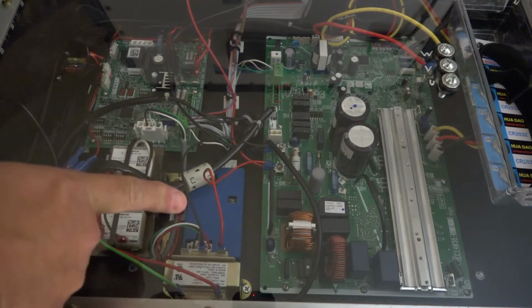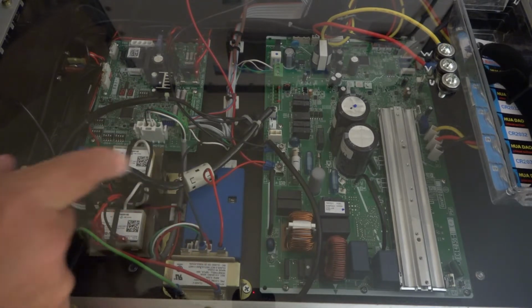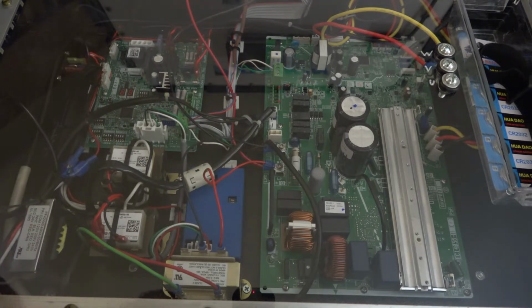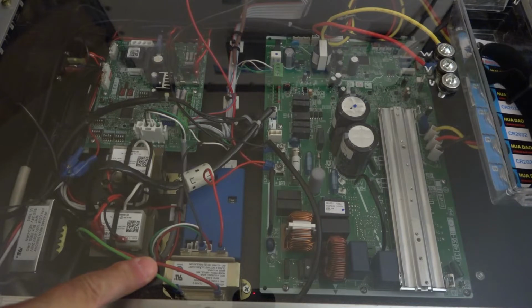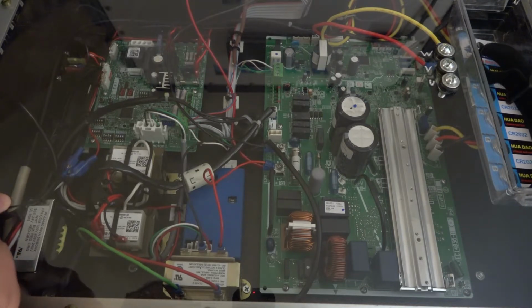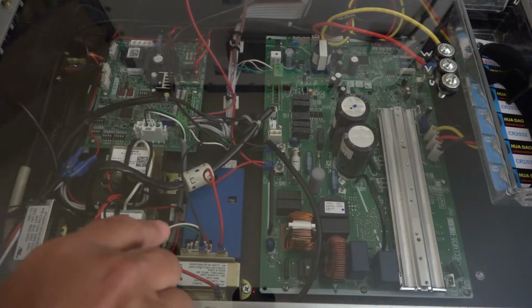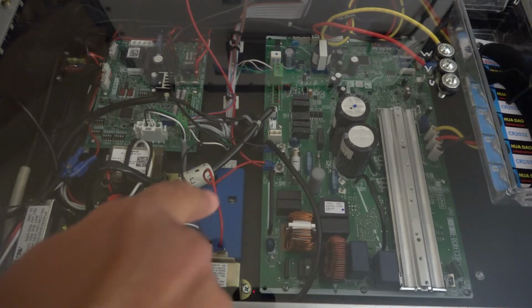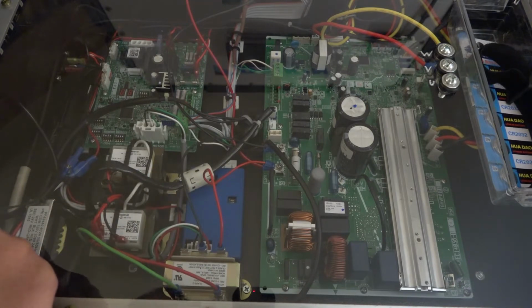The little blue box here is an ECM motor simulator. Now what I've done, I've got 120 volts powering this box. So I'm bringing 120 volts into a 40 VA transformer. 120 primary, secondary is 24 volts. And then I'm running it over to a 240 volt 40 VA transformer. So 24 volts off the 110 or 120 transformer over to 24 volts on the 240, and what comes out of it is about 226 volts at about 5 or 6 amps. That's about all the power that I can get out of it.